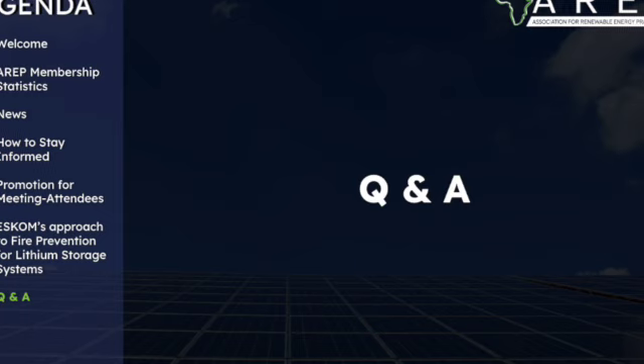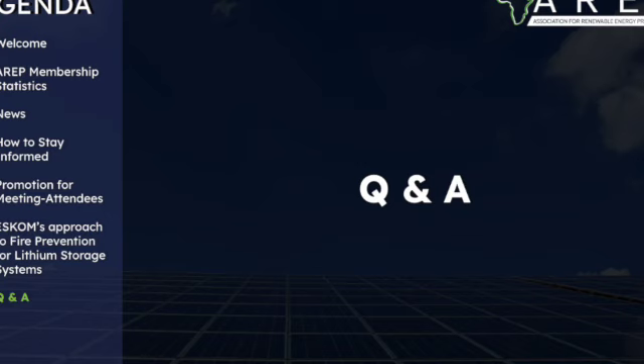Some of the containers on the market now are very nice because they're not walk-in units, you access everything from the outside. That helps with zoning, so your light fittings, fire detection, and other electronic equipment don't necessarily have to be HAZLOC rated. But it is something you must consider for large scale installations, whether it's a hazardous location based on what you have, and then typically I'd expect it to be zone 1 or 2, not zone 0. All your other electrical equipment would then have to be EX rated in relation to your zoning according to SANS 10108.